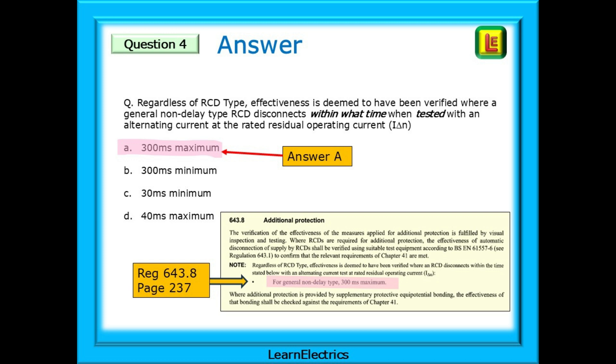In other words, the RCD tripping current shown on the device. The answer is A, 300 ms maximum, regulation 643.8, on page 237.